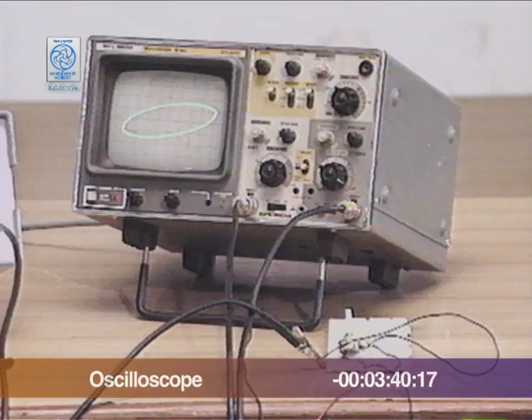Sir, what are the precautions needed when we are operating a CRO? First is we must check the power supply. Here we are giving the power supply single phase, that is 230 volts, and 50 hertz mains supply, that is the domestic supply. So we have to apply that much voltage to give the power to this one. And that socket must be earthed such that there is no shock hazard on this CRO, because this body and all these terminals are being earthed, so there must be an earth terminal on the socket.